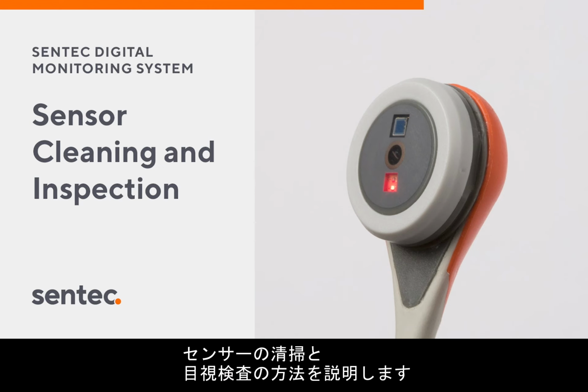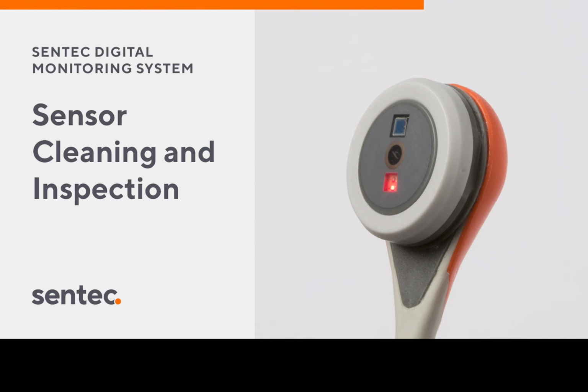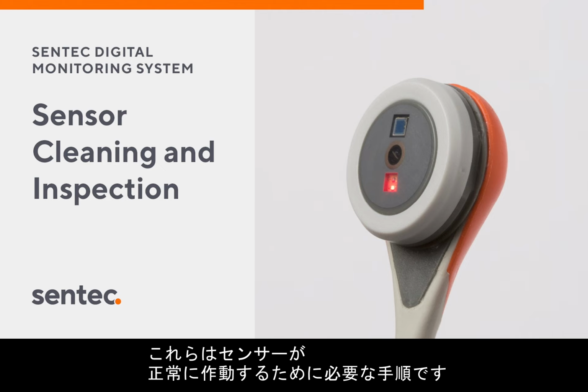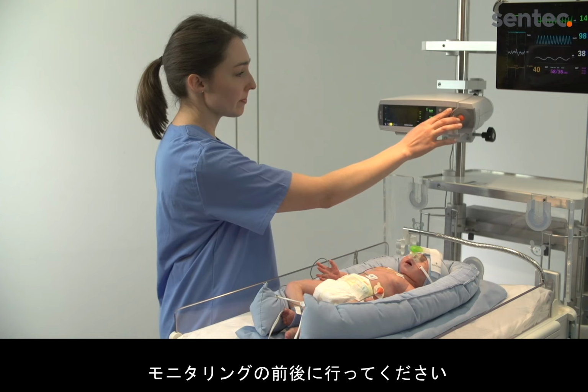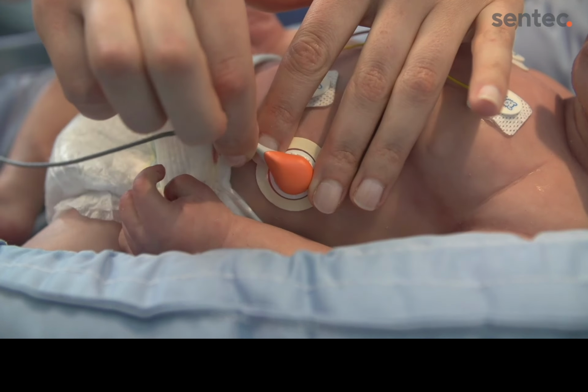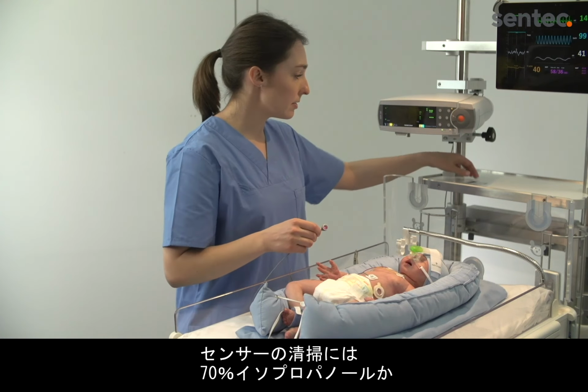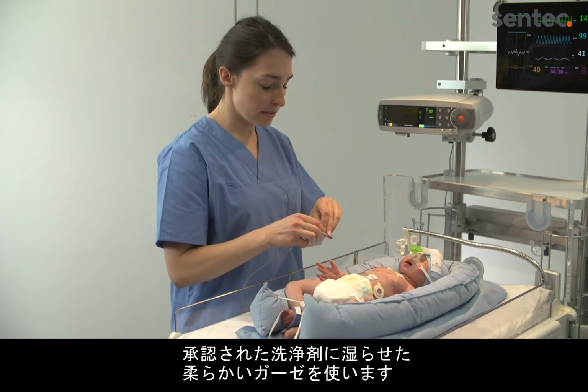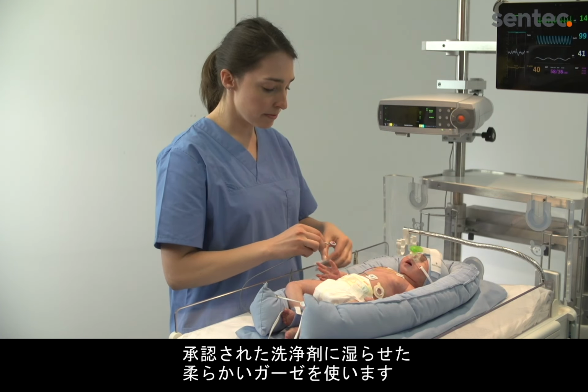This video will demonstrate the basic cleaning and visual inspection steps necessary to keep the Sentec sensor in good working condition. Follow these steps between each monitoring period. To clean the sensor, use a lint-free gauze soaked in 70% isopropanol or other approved cleaning agent.